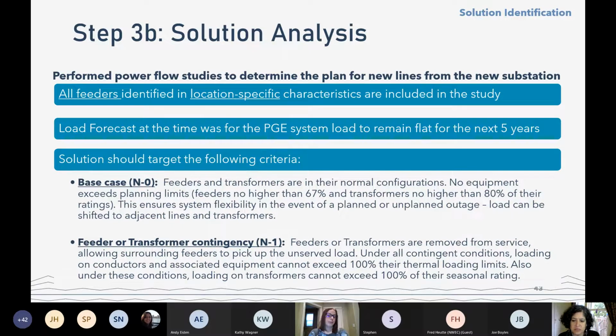We apply the same criteria discussed earlier with the base case: feeders should not exceed 67% and transformers should not exceed 80%. We also run contingency analysis, so that when a feeder or transformer is removed from service, we can still pick up all of that load during peak conditions.